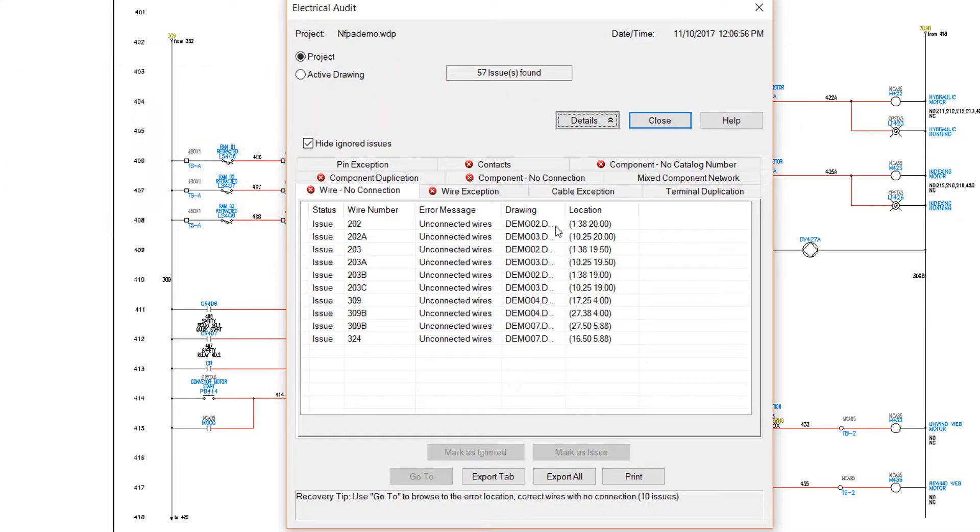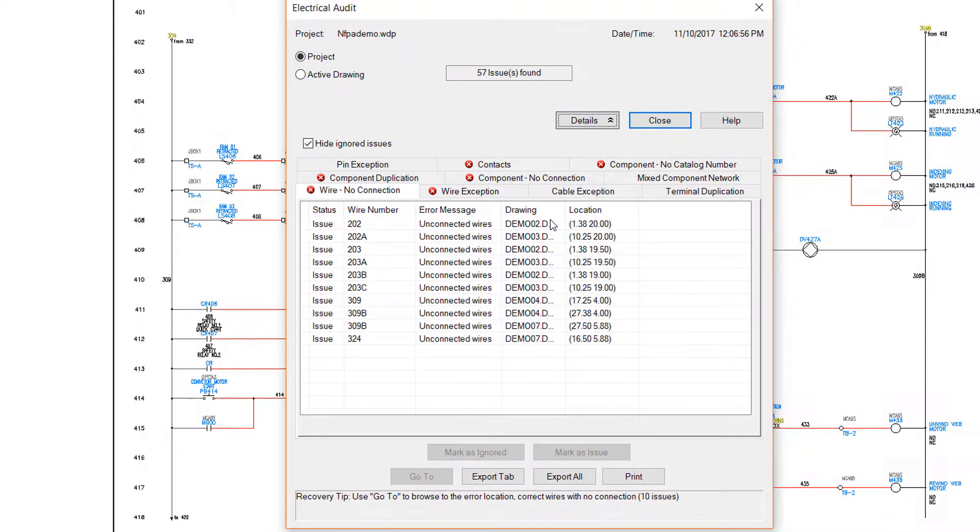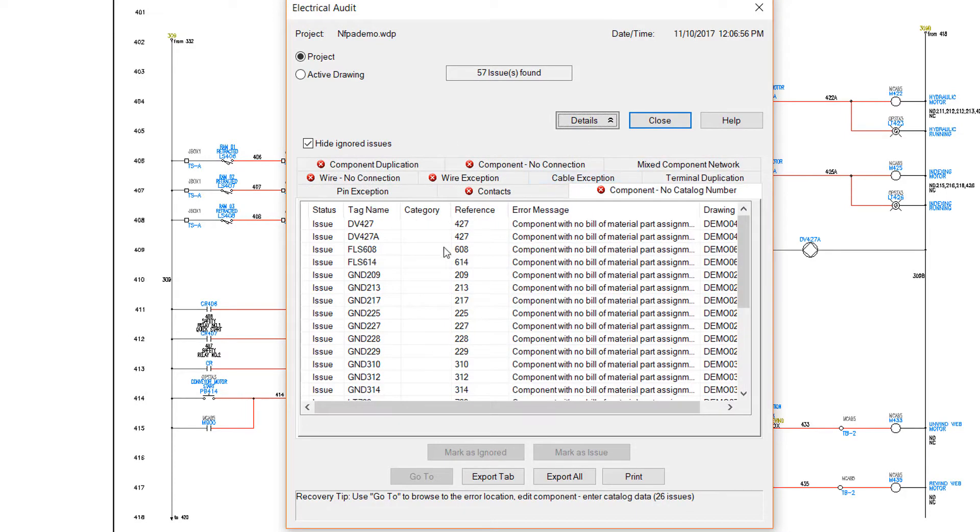The issues listed may not be actual problems, but are things that AutoCAD Electrical is not sure of. Some categories, like Component No Connection, will almost always have entries listed, since you will seldom connect a wire to every connection on every component. If issues are found in other categories, such as Component No Catalog Number, they will usually require some attention before releasing the project.